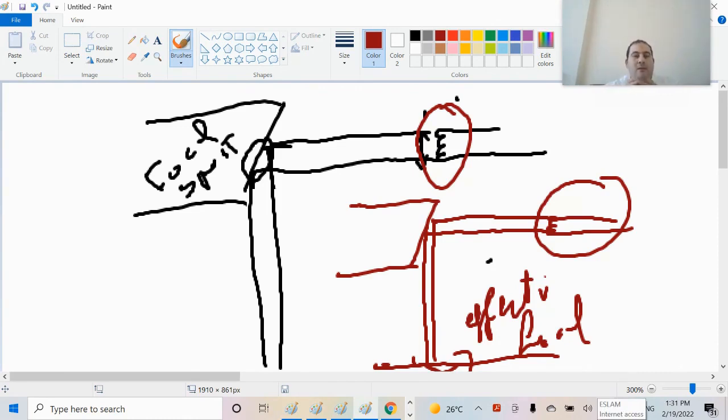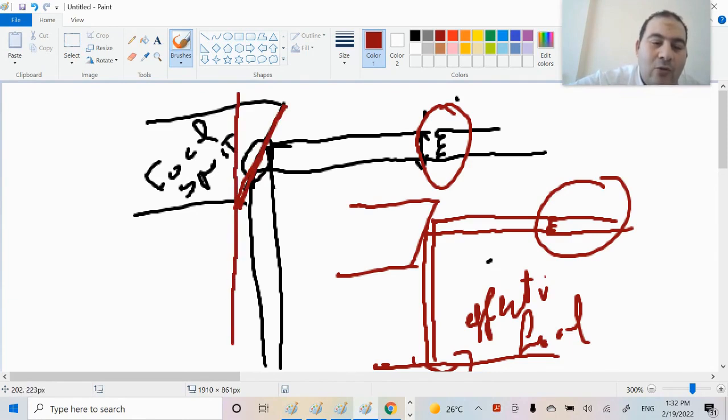What is their relation to the anode angle? If you look closely, you'll see that the anode face forms a slope with the line which is the central line of the central beam itself. This angle is called the anode angle.